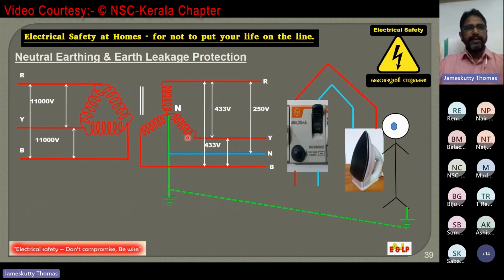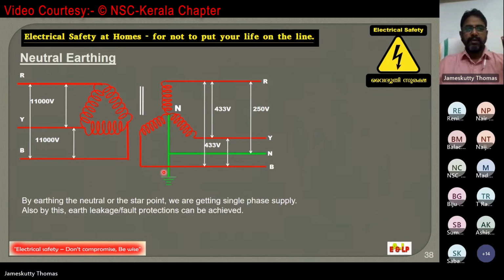So by creating the neutral point, we are mainly getting 2 benefits. First, we can get a single phase supply. We can get a single phase connection between the neutral and one of the three phases, and thereby we can operate our single phase loads. We can get 250 volts or 230 volts. That is one of the benefits of earthing this neutral. Additionally, by this neutral, we can get earth fault or leakage protection.